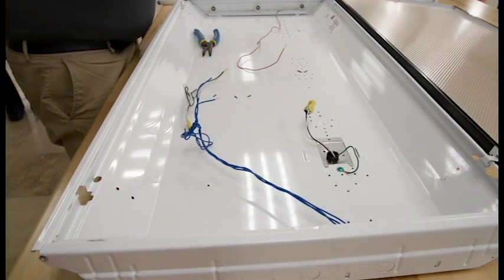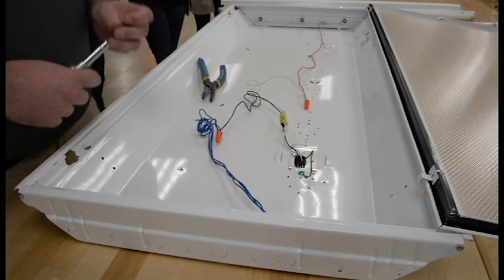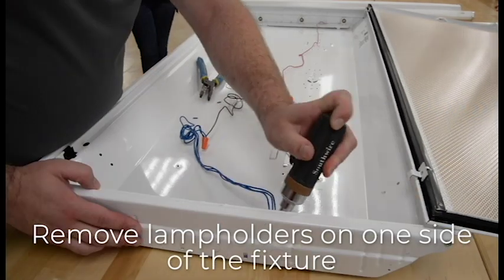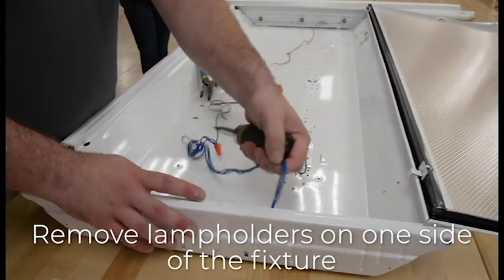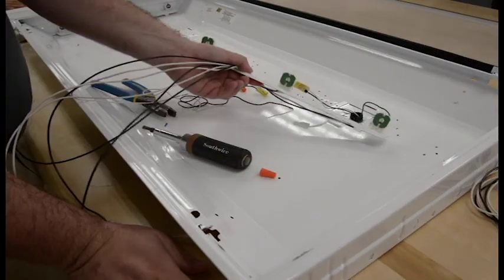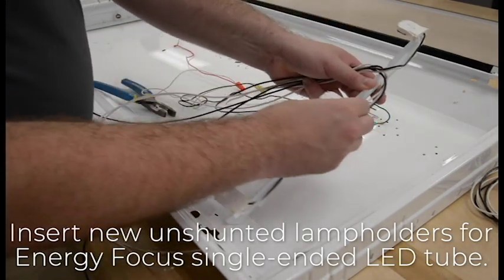To use a single-ended direct wire lamp, you will need to replace one set of shunted lamp holders with a set of unshunted lamp holders. Remove lamp holders on one side of the fixture, then replace the previously removed shunted lamp holders with new unshunted lamp holders from Energy Focus.